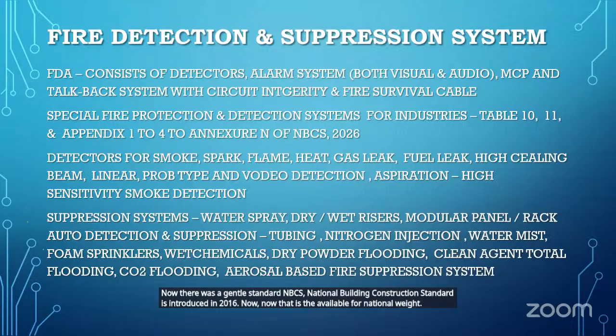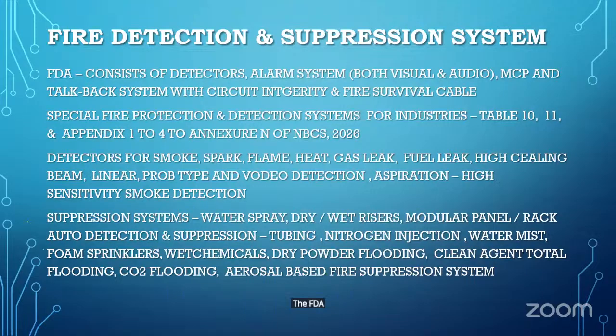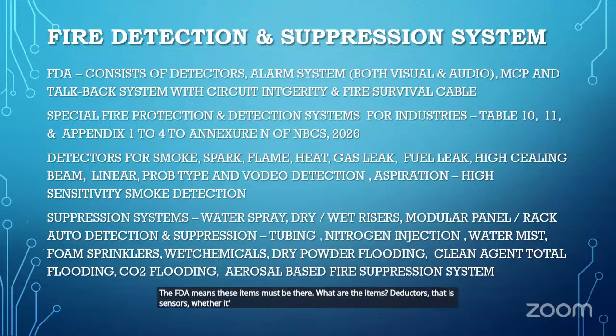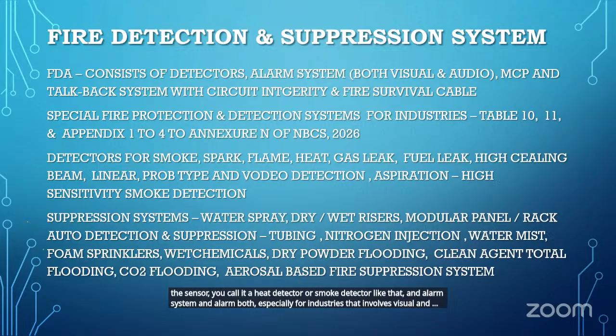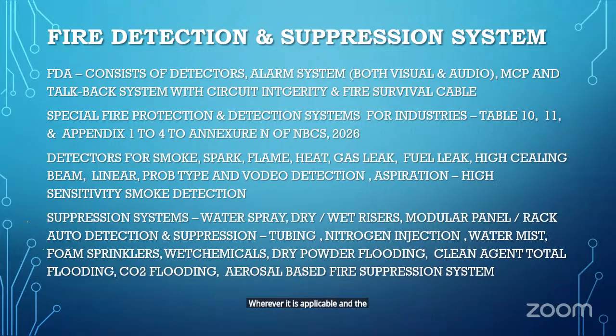So as per the previous NBC and the current NBCS, for the FDA these items must be there. What are the items? Detectors, that is sensors, whether it's a heat sensor, smoke sensor or flame sensor, whatever the sensor, you call it a heat detector or smoke detector. And the alarm system, especially for industries, that involves visual and audio wherever applicable, and the MCP and talkback systems with circuit integrity.